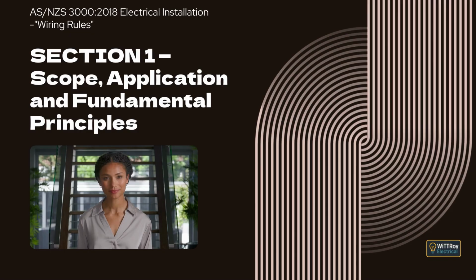Clause 1.4.63 is extraneous conductive part. This is a conductive part that is not part of the electrical installation, but that can be at the electrical potential of the local earth. Examples include metal water or gas pipes, heating system pipes, metal building components, steel-framed structures, reinforced concrete floors or walls, tiled surface coverings, conductive fittings in bathrooms, and metal pipes.